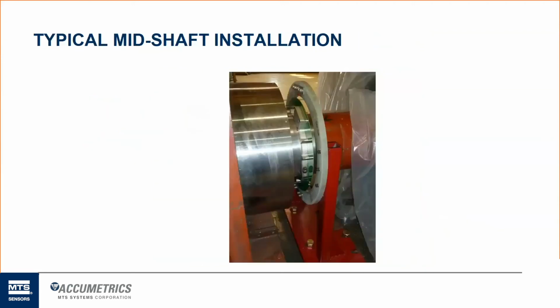So here's a typical midshaft installation, what it may look like. So again, this is the coupling flange that is going to mate up to the generator, which would be off to the left, which would have an identical coupling flange that they then get all bolted together. So you have to be able to get the electronic bus connection, the negative and positive side of the field, from the exciter over to the generator. And this is how they decouple it from that. And I'll show you in the next few slides how they get that electrical connection.